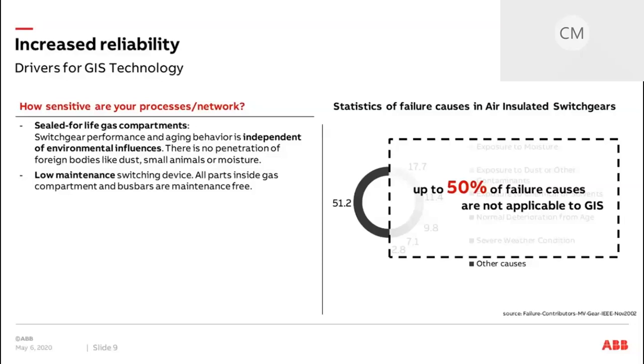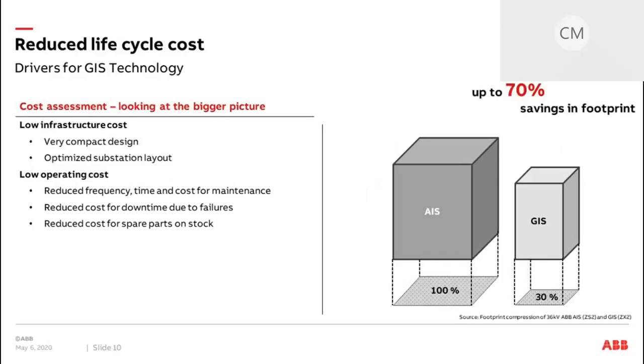In addition, it's a low maintenance switchgear, so all high voltage parts inside the gas compartments are practically maintenance free. This also accounts to reduced life cycle costs, because we have lower operating costs due to the reduced frequency, time, and cost for maintenance, for the reduced cost for downtime due to failures, as well as because we have less failures, we need less spares on stock.